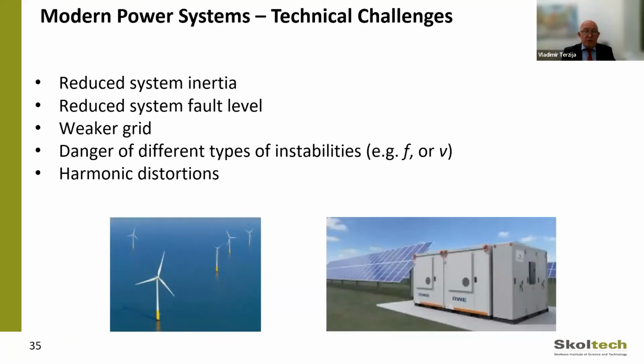One issue from the perspective of the electrical power system, when it comes to high penetration of converter-interfaced generation like wind farms, is type 3 and type 4. Both have power electronics-based components; particularly type 4, meaning the wind farm is fully connected to the grid via inverter. This non-synchronous connection causes consequences to system dynamics.